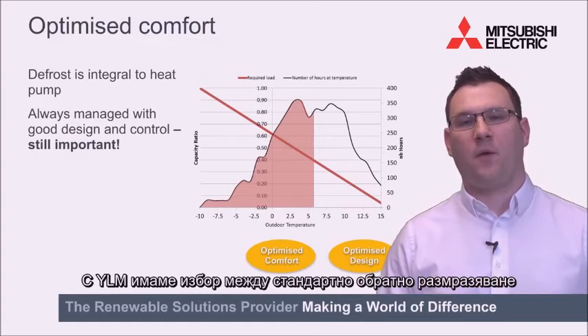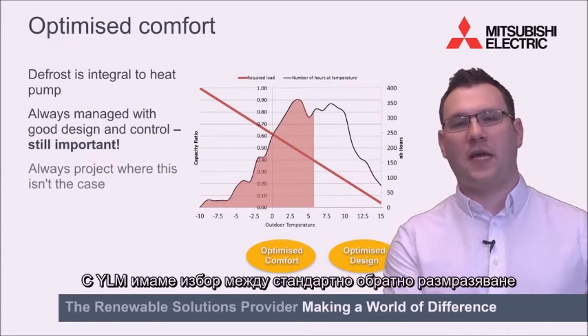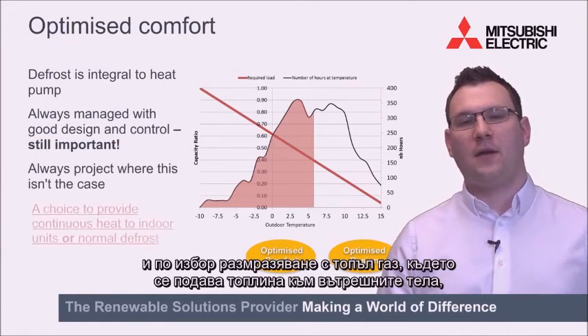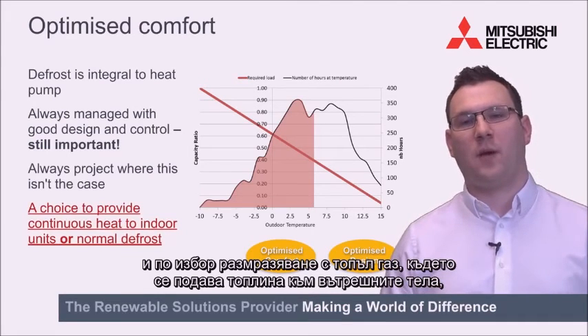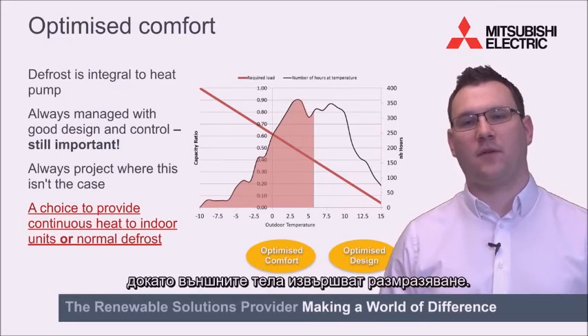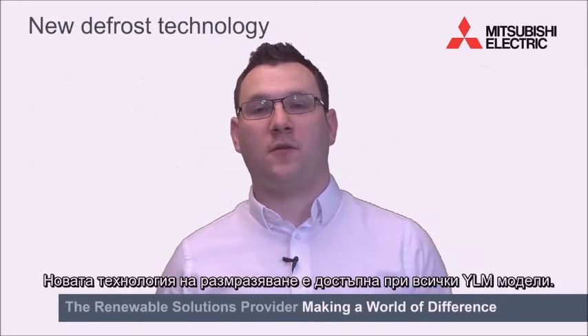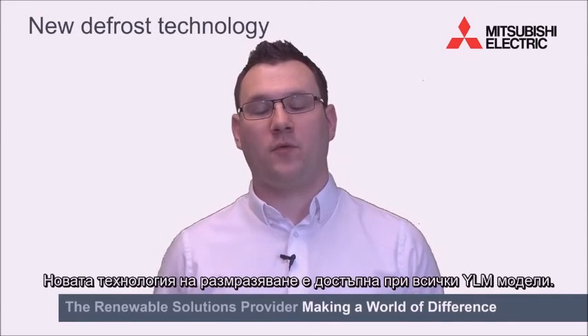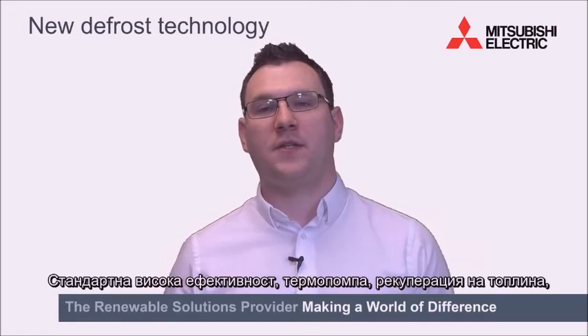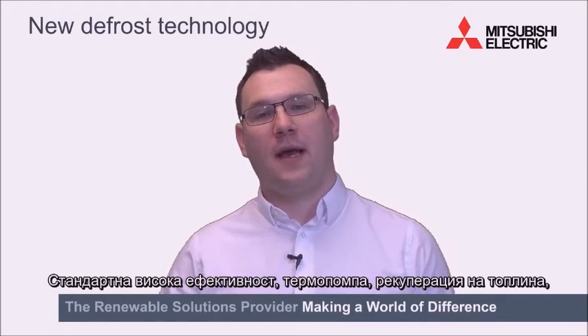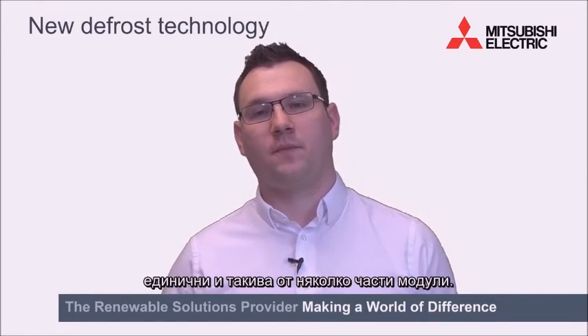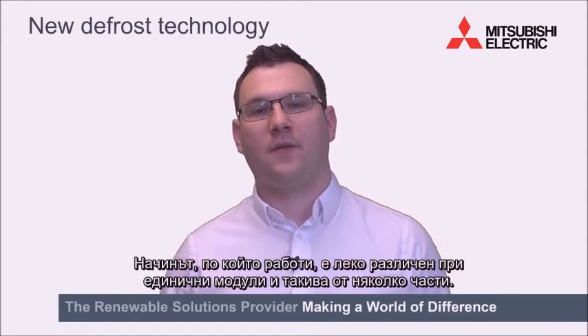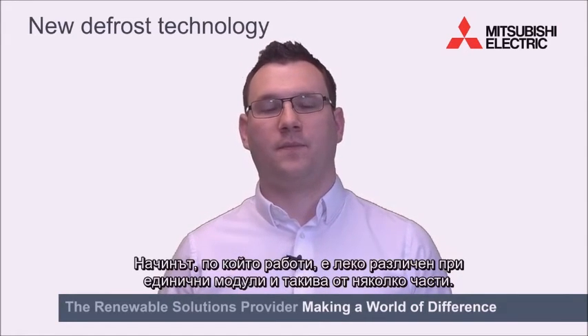With YLM we have a choice between your standard reverse defrost and an optional hot gas defrost, whereby you're providing heat to the indoor units while the outdoor unit does its defrost. This new defrost technology is available in all YLM models: standard, high efficiency, heat pump, heat recovery, and single and multiple modules. The way it works is slightly different between a single and a multi-module.